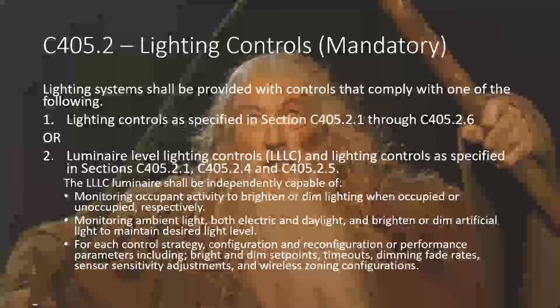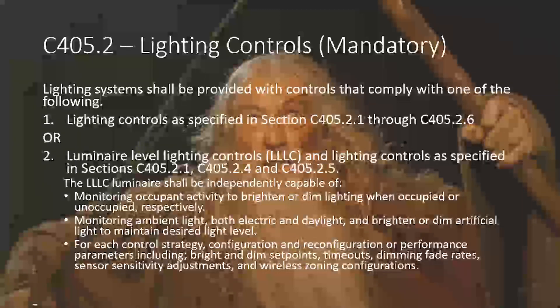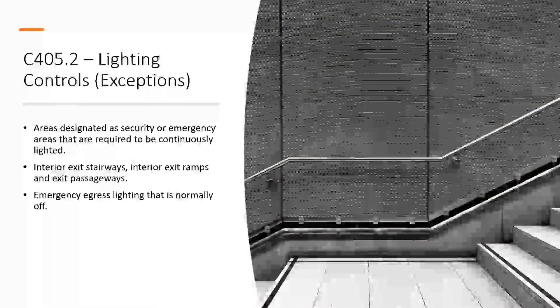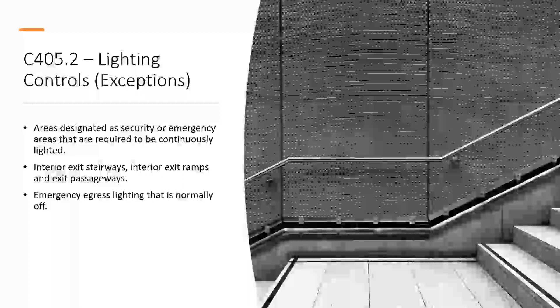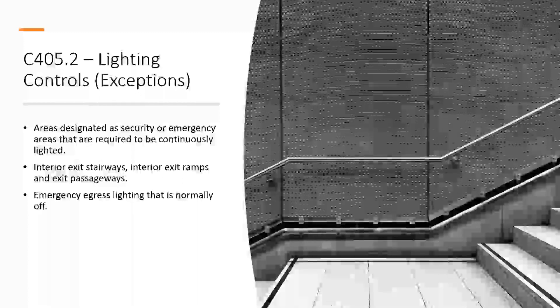Mandatory lighting controls: lighting systems shall be provided with controls that comply with one of the following — either go through sections 405.2.1 to 405.2.6, or use luminaire level lighting controls. I'll keep coming back to LLC to show how they simplify code compliance. Exceptions include areas designated as security or emergency areas that are required to be continuously lighted — code does not define 'security or emergency area,' so that's up to you based on building type and context. Also excepted are interior exit ways, exit ramps, exit passageways, and emergency egress lighting that is normally off — meaning they are controlled independently of general lighting.